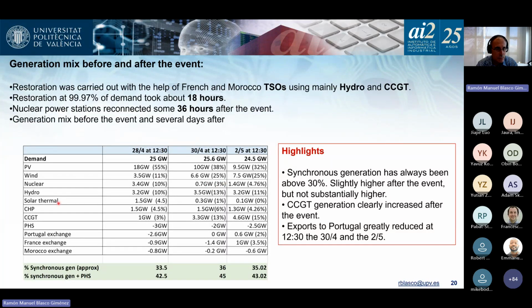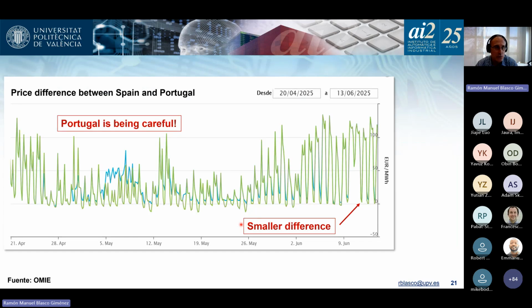But the main difference is CCGT. You see, the CCGT production is treble, just to keep an enhanced safety margin regarding both frequency and voltage control. And exchanges with Portugal went from almost 3 gigawatts to 0. So the Portuguese colleagues didn't trust Spanish colleagues. And that's something that can be seen, but inertia was more or less the same in all cases. So it is clear that it wasn't in this case an inertia problem.